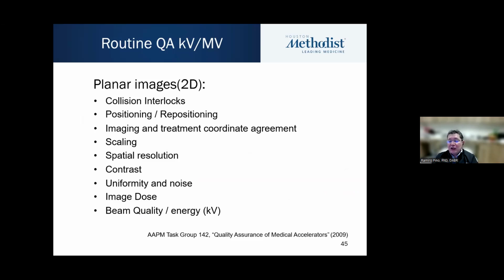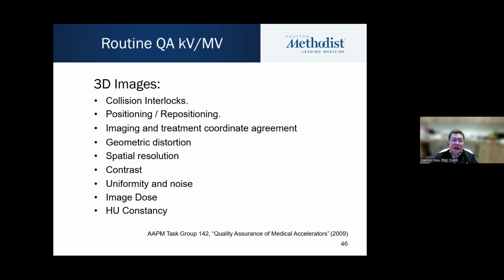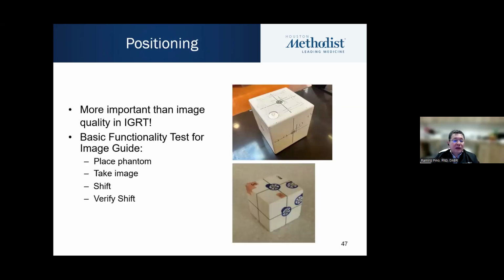Remember, you're now tracking or guiding the positioning of your patient based on your imaging system, but at the end, you're delivering from a different source, and it's important to make sure that those two isocenters agree. Scaling is obviously very important: spatial resolution, contrast, uniformity and noise, image dose, and beam quality and energy. For 3D imaging, again, very similar: collision interlocks, position repositioning, isocenter agreement, distortion, and so on and so forth. And many of these tests are very similar to the ones I mentioned for the CT simulation.